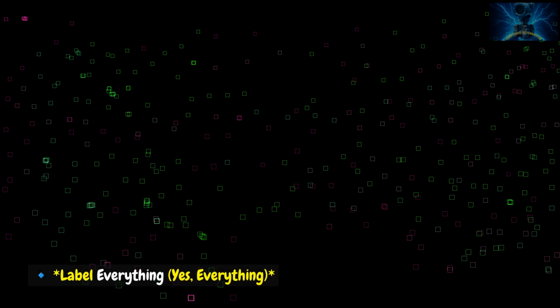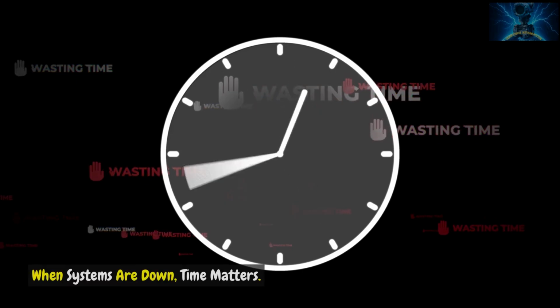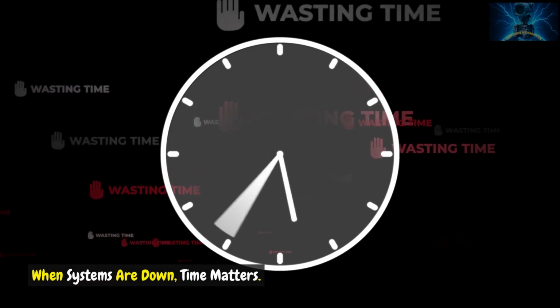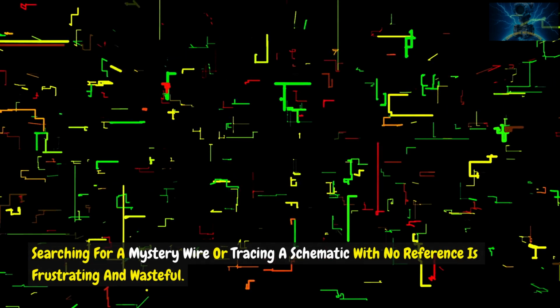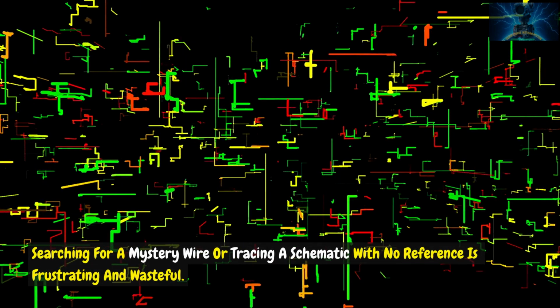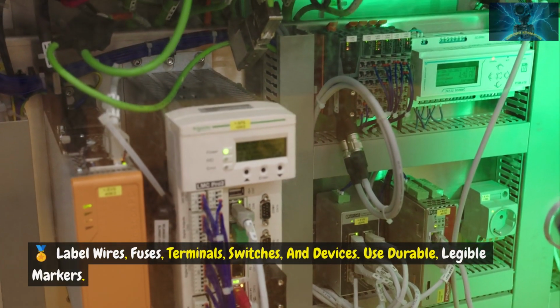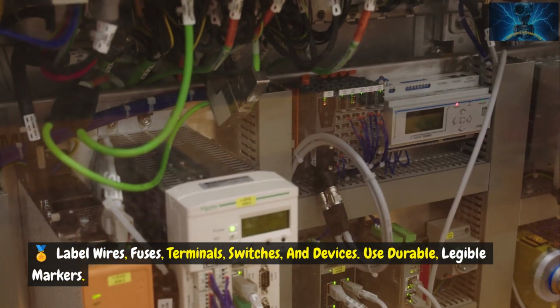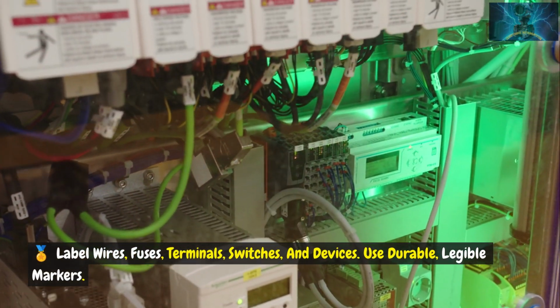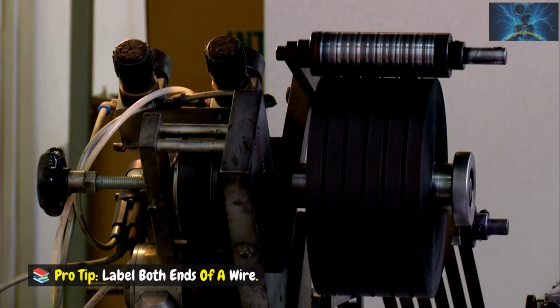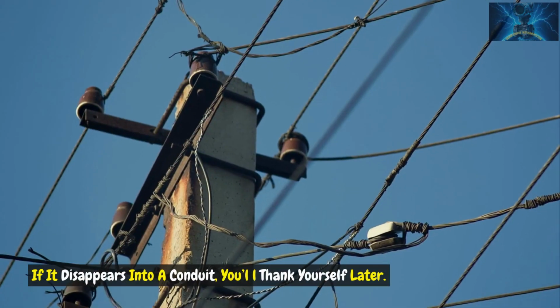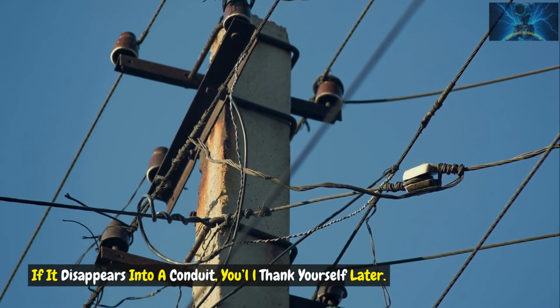Label everything. Yes, everything. When systems are down, time matters. Searching for a mystery wire or tracing a schematic with no reference is frustrating and wasteful. Label wires, fuses, terminals, switches, and devices. Use durable, legible markers. Pro tip: label both ends of a wire. If it disappears into a conduit, you'll thank yourself later.